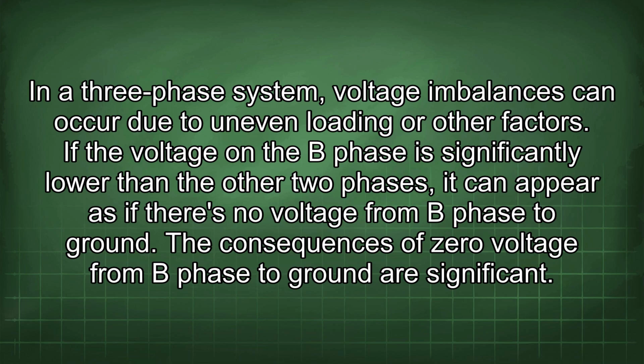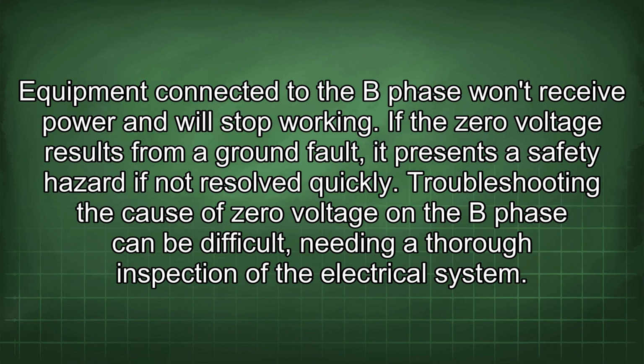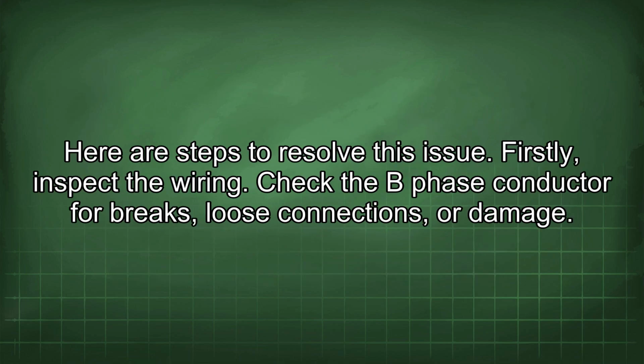The consequences of 0 voltage from B phase to ground are significant. Equipment connected to the B phase won't receive power and will stop working. If the 0 voltage results from a ground fault, it presents a safety hazard if not resolved quickly. Troubleshooting the cause of 0 voltage on the B phase can be difficult, needing a thorough inspection of the electrical system. Here are steps to resolve this issue.